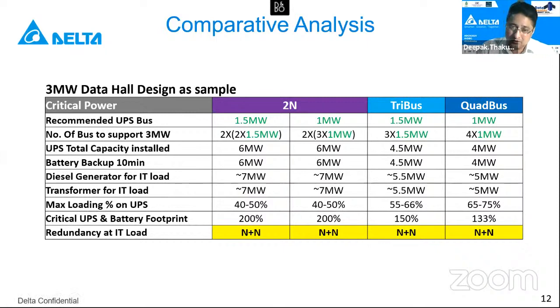You need to have almost 7 megawatt of the DG as well as the IT transformer, which is the main transformer, which is coming up. And still you are only doing the maximum loading of 40 to 50% on one side. And the critical UPS and battery footprint is double, 200%. And the redundancy achieved by your design is still N plus N, which is 2N architecture. Now, similarly on the tri-bus, if you see, the same architecture is being done with 3 into 1.5 megawatt UPS systems. And that means you also need a lesser DG capacity. You also need a lesser backup at say 4.5 only, because the installed total capacity of the UPS is 4.5 megawatt. So instead of 6 megawatt on battery design, now you have 4.5 megawatt. And the same thing, you see 55 to 66% utilization.